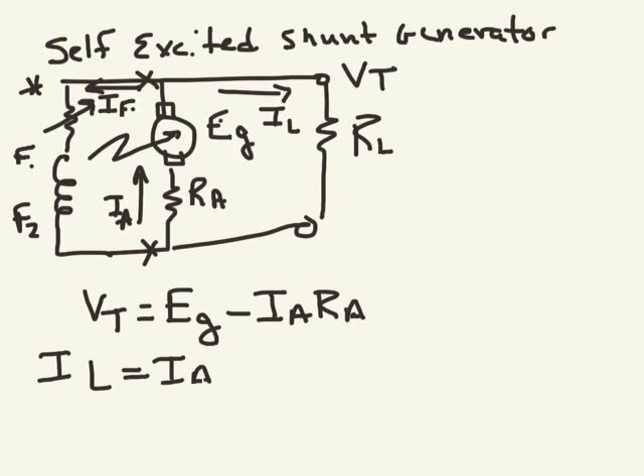And that's not exactly the case here, is it? That armature current, now we're going to lose just a little bit of current to the field. So if we're talking at rated voltage, we're talking about losing, for our motors, 19 amps rated current to the terminal, we're going to lose 600 milliamps of field.